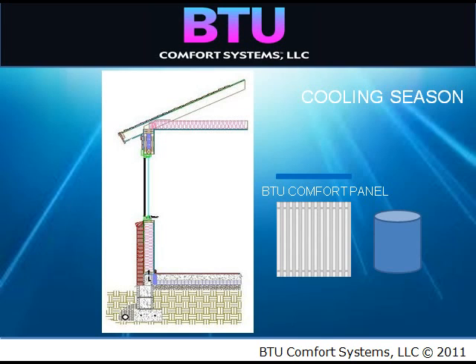Because the panels are located at the ceiling, there is no limitation to the panel's surface temperature. Unlike a floor system that is limited to 62 degrees at the surface, which subsequently limits the total output conditioning available, BTU Comfort panels can achieve larger cooling loads by allowing a lower panel surface temperature. The dew point is monitored zone by zone, and the system has the ability to close the supply water circulation. Both heating and cooling can be achieved from a single source ceiling radiant system.